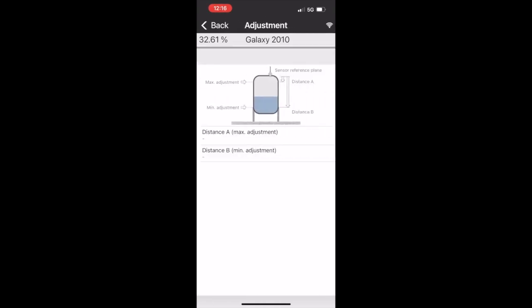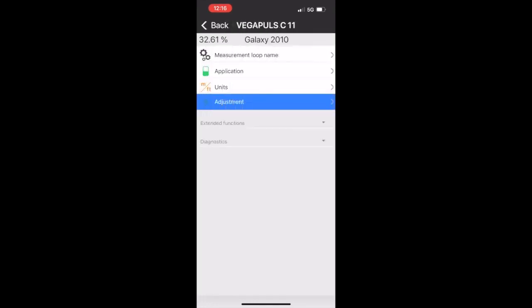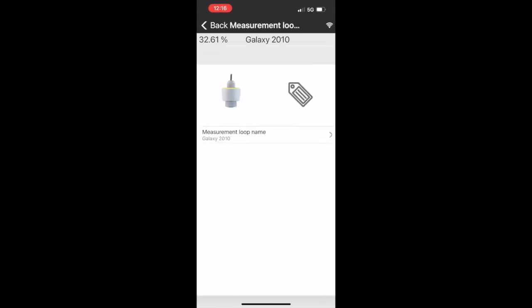Go back and click Adjustment. This will let you enter distance A and distance B. For distance A, put in the value of 0, and for distance B, measure your tank from the very top to the top of your probe, not to the top of the tank. You can also go back and select Measurement Loop Name and change the name of the sensor.